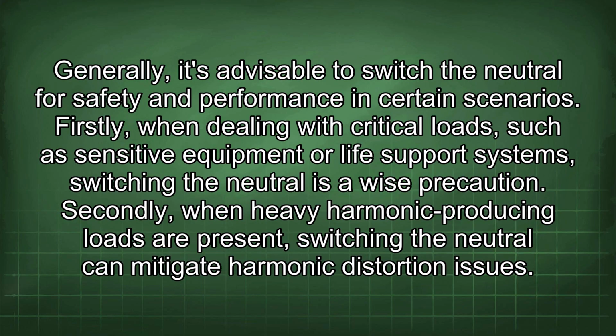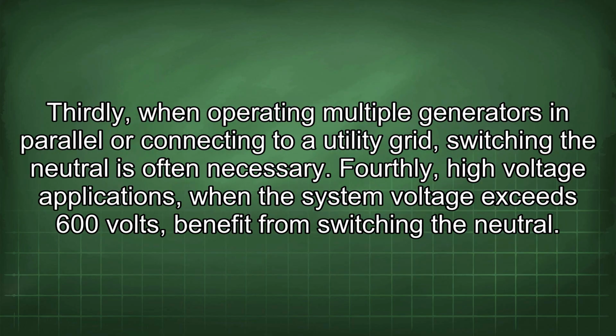Generally, it's advisable to switch the neutral for safety and performance in certain scenarios. Firstly, when dealing with critical loads, such as sensitive equipment or life support systems, switching the neutral is a wise precaution. Secondly, when heavy harmonic producing loads are present, switching the neutral can mitigate harmonic distortion issues. Thirdly, when operating multiple generators in parallel or connecting to a utility grid, switching the neutral is often necessary. Fourthly, high voltage applications, when the system voltage exceeds 600 volts, benefit from switching the neutral.